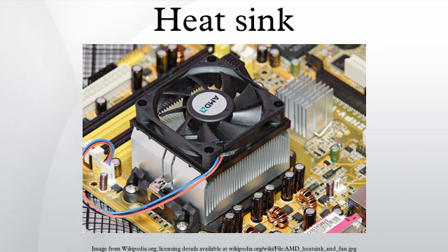Ducted flow is where the air is forced to flow through a channel which fits tightly over the heat sink. This makes sure that all the air goes through the channels formed by the fins of the heat sink. When the airflow is not ducted, a certain percentage of airflow will bypass the heat sink. Flow bypass was found to increase with increasing fin density and clearance, while remaining relatively insensitive to inlet duct velocity.